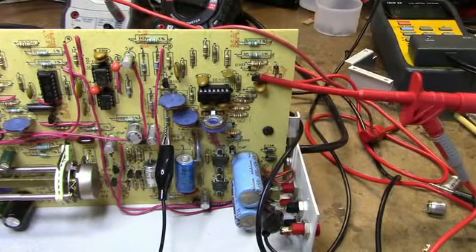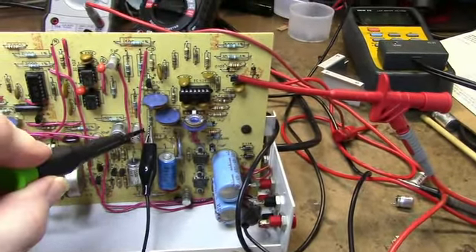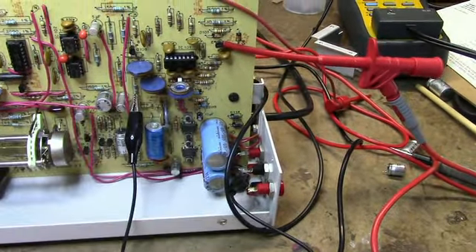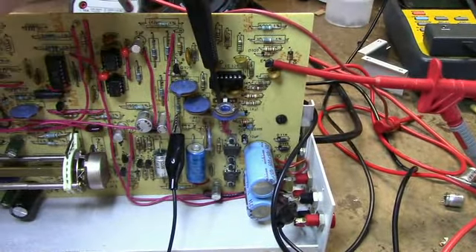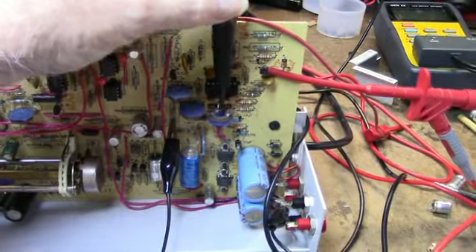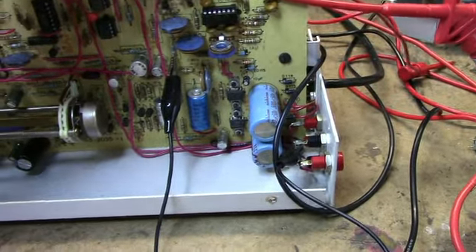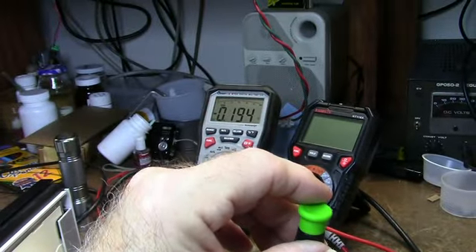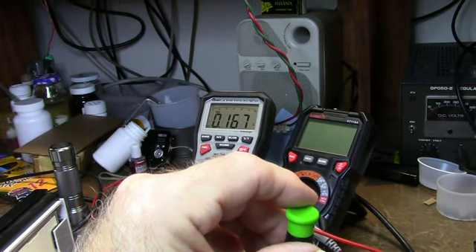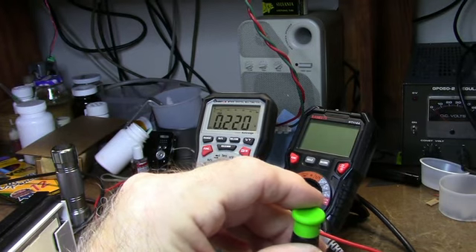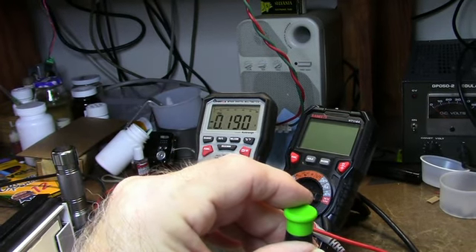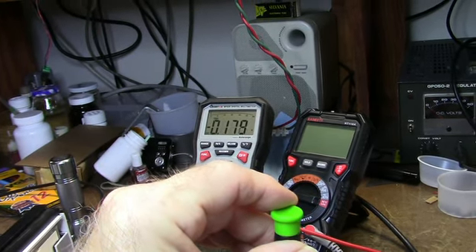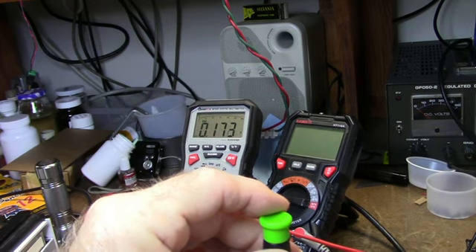To adjust the AC to DC converter, you connect a jumper from the bottom of this 10K resistor to the negative lead. Then you center adjustment A2 to the midpoint and adjust A1 to zero. It's very, very touchy. It'll go from negative to zero to positive and you're not going to set it right on zero. Get it as close as you can.